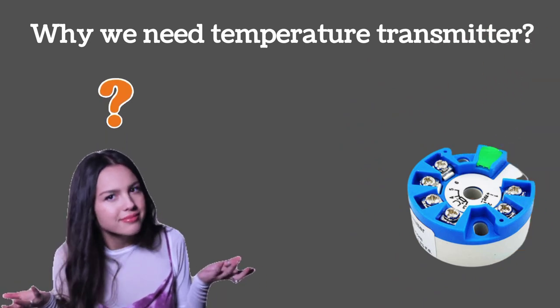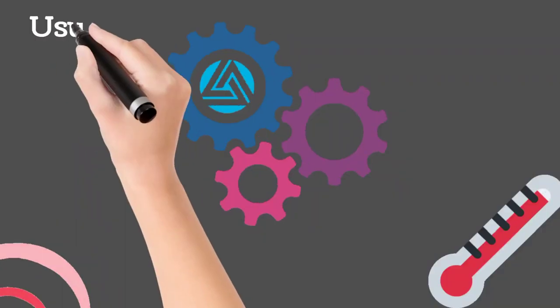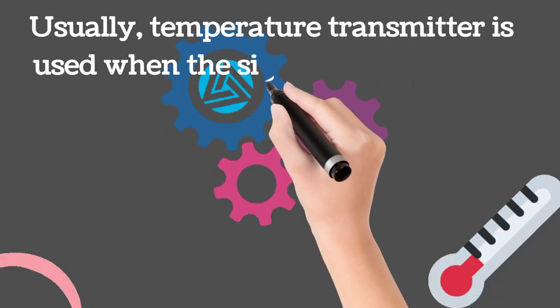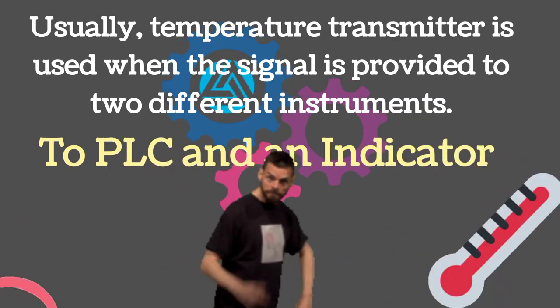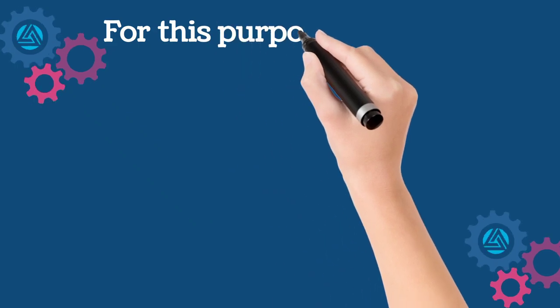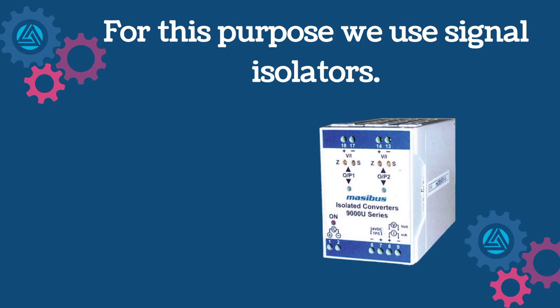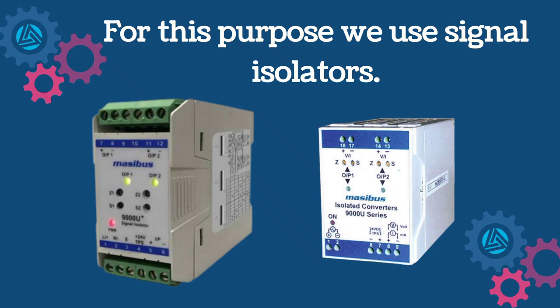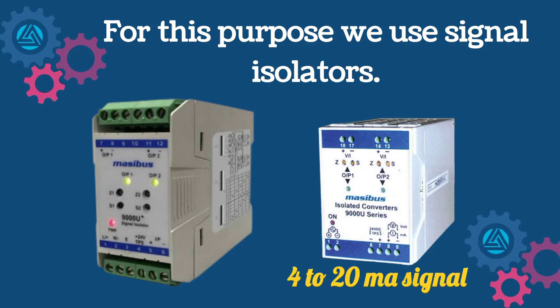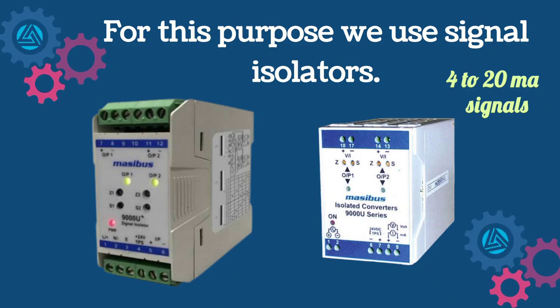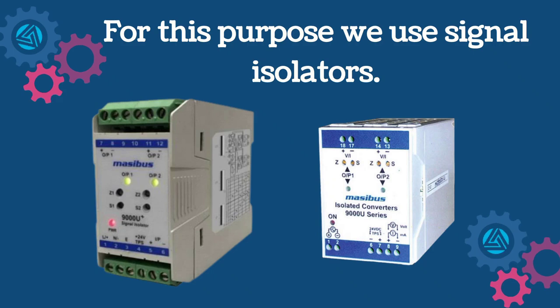Now we will discuss why we need temperature transmitters while we can connect RTD or thermocouple directly. Usually, a temperature transmitter is used when the signal is provided to two different instruments or more than one instrument, like a PLC and an indicator. To provide a transmitter signal to more than one instrument, signal isolators are used. Signal isolators are used in PLC panels and have one input and two or four outputs. The input signal is 4 to 20 mA and the output signals are also 4 to 20 mA, so two outputs may be connected — one at PLC and another at an indicator.